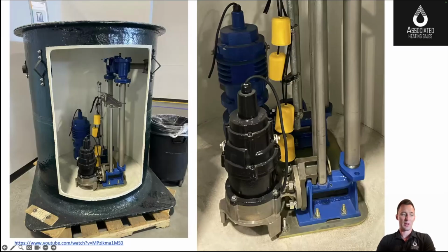So what the rail system does is it establishes a permanently installed floor elbow, discharge pipe, and guide rails for this pump to go up and down on to be installed. The pump sits on this floor elbow with the cleat, and the cleat and pump are the only thing that run up and down and out of the pit. So everything else is permanently installed. So it eliminates that large length of pipe that is going to be impossible to get out.